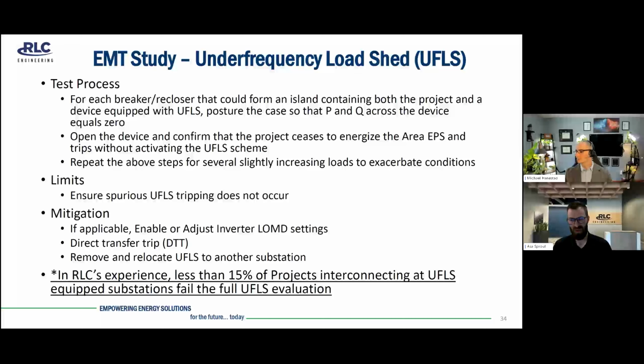So we aim to ensure that DER doesn't cause UFLS nuisance tripping, as these devices can become locked out, require manual restoration, and in general, for protection philosophy, you don't want devices tripping on things that aren't actually happening. So this test process is fairly similar to ROI, but with more sensitivities to load to create conditions where the project may still be energized, but UFLS could trip that protective device.